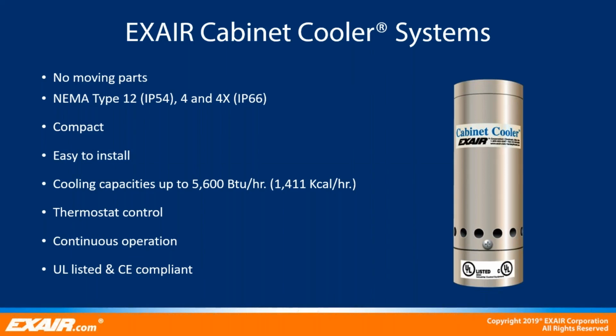NEMA Type 12, 4, and 4X models are available that are very compact and mount in just minutes through an ordinary electrical knockout. Available in a wide variety of cooling capacities, ranging from 275 BTUs per hour for our smallest unit, up to 5,600 BTUs per hour for our largest dual system. Thermostat control systems are the most efficient way to operate a cabinet cooling solution, as they limit compressed air use by operating only when the temperature inside the enclosure approaches critical levels. Continuous operating systems are recommended when constant cooling and constant positive pressure inside of a panel are required. In addition, EXAIR Cabinet Coolers systems are also UL listed and CE compliant.